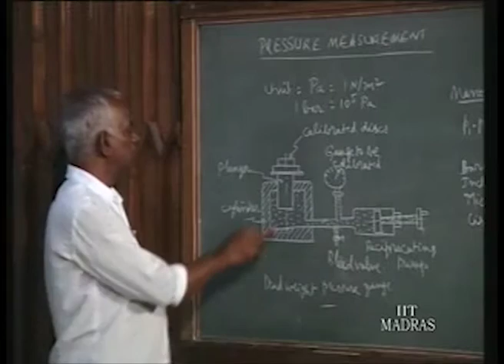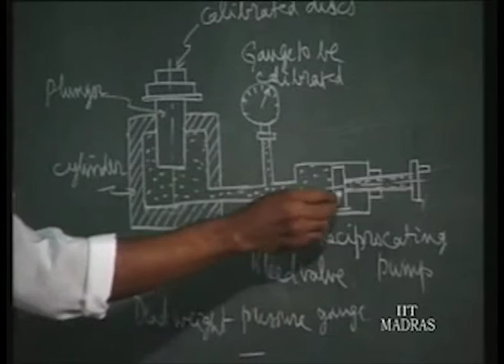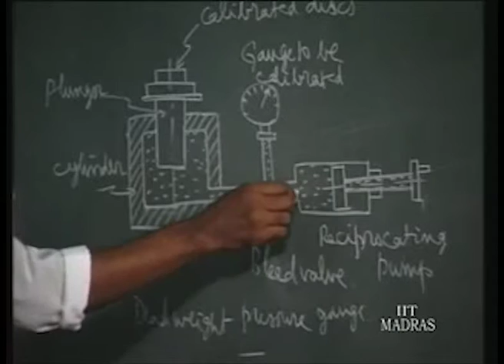Now the instrument normally used for calibration of pressure gauges is the dead weight pressure gauge. The principle of functioning is like this: there is a plunger and cylinder, and a pump to develop pressure in the liquid, and the gauge to be calibrated is fixed here. By rotating this piston we can move the piston forward or backward, thereby developing or releasing the pressure in the liquid in the setup.